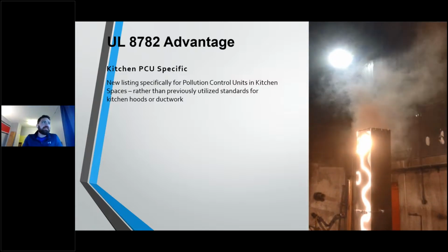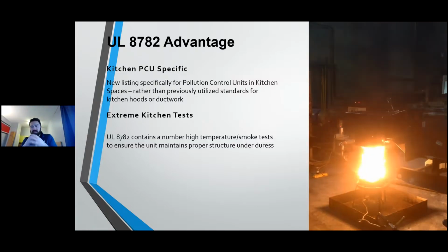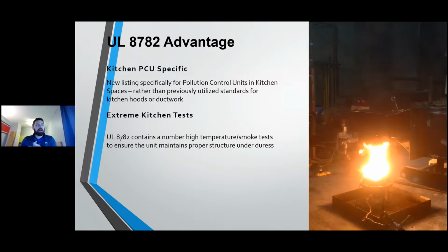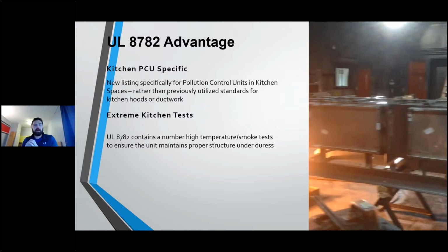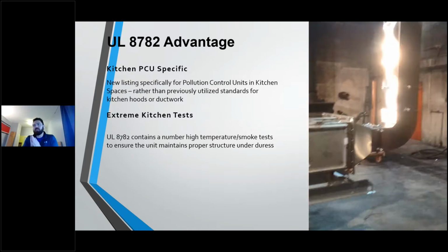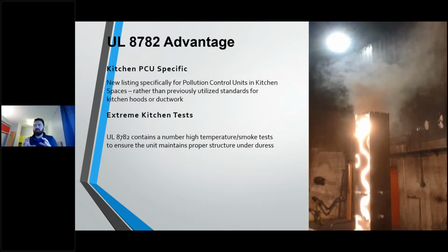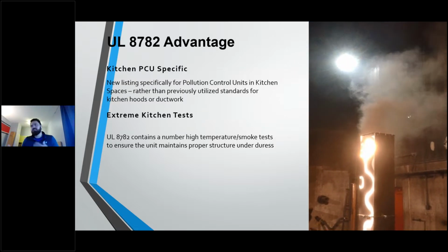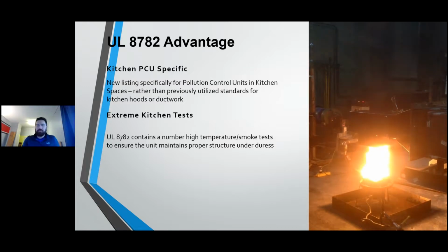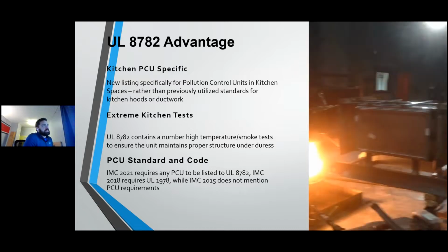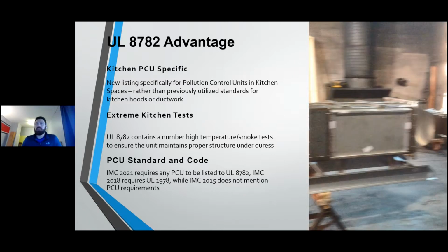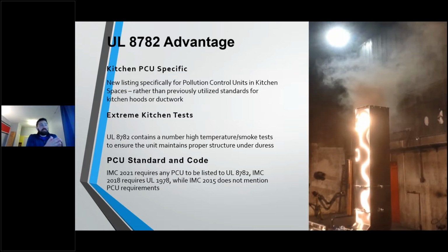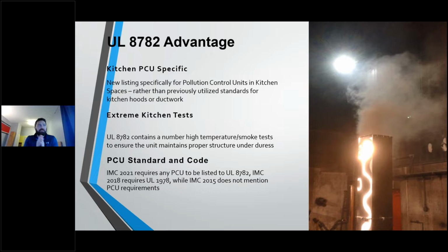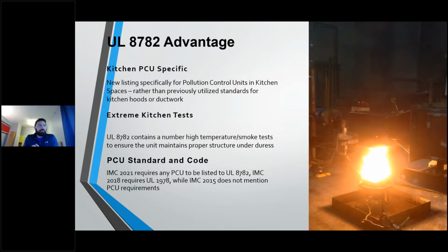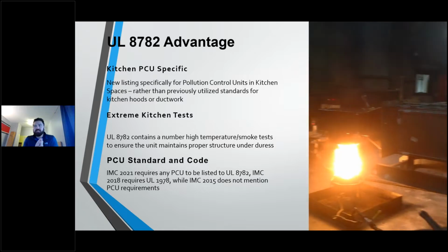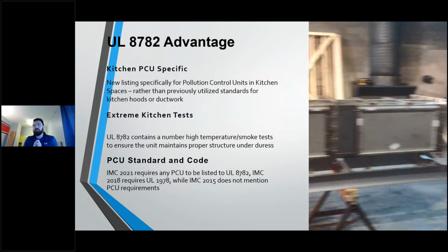Now we have the UL 8782. It's an actual UL certification for high temperature and smoke tests to ensure that the unit maintains proper structure under duress. And it's actually listed for pollution control units, as opposed to that weird murky line of UL 710, ETL, UL 1978 for grease duct. This is a defined line. So where did this all come from? IMC 2021 requires any PCU to now be listed to UL 8782. IMC 2018 required that PCUs be listed to 1978, which was a grease duct standard. And then 2015 didn't mention PCUs at all. So it's important to note that PCUs from IMC 2021 forward are under the UL 8782 listing.